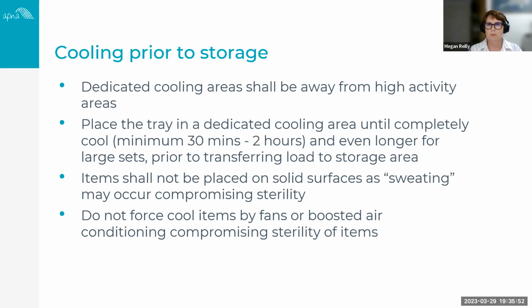So when you bring items out of the steriliser, don't ever place them straight down onto a solid surface. You need to put them onto something like a cake rack or some sort of surface where we can get good ventilation, good air circulating around, and that will minimise the effect of sweating. Because if we have sweating, it means we have moist packaging, and we can't use instruments that are in moist packaging. And remember, don't ever try to force cool items. Sometimes I've seen little portable fans, or items being placed under the air conditioners with the vents turned down to try and speed up the cooling process. It compromises the sterility of items, and you get air turbulence. So it has the ability to actually move microorganisms around, particularly from dirty to clean. And we've already talked about not doing that.